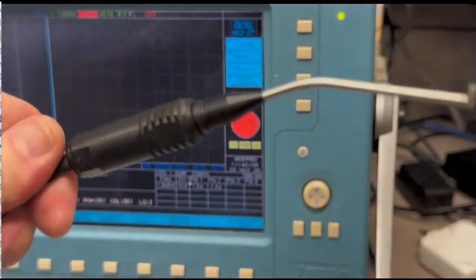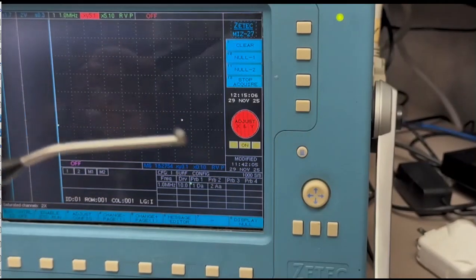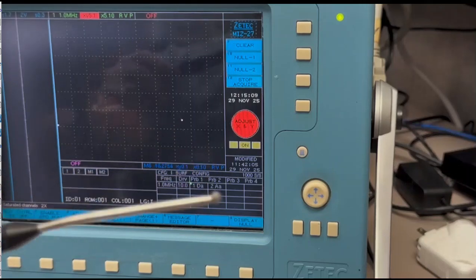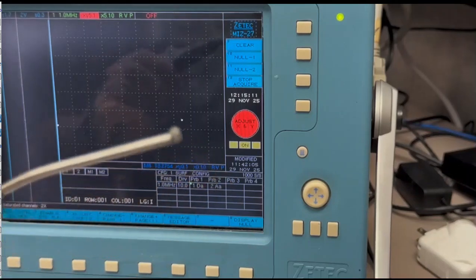Then I have a Zetec pencil probe. That's a tiny coil there in the head. That's because we're looking for tiny flaws. You wouldn't be looking for tiny cracks with a big wide coil. You'd miss them.